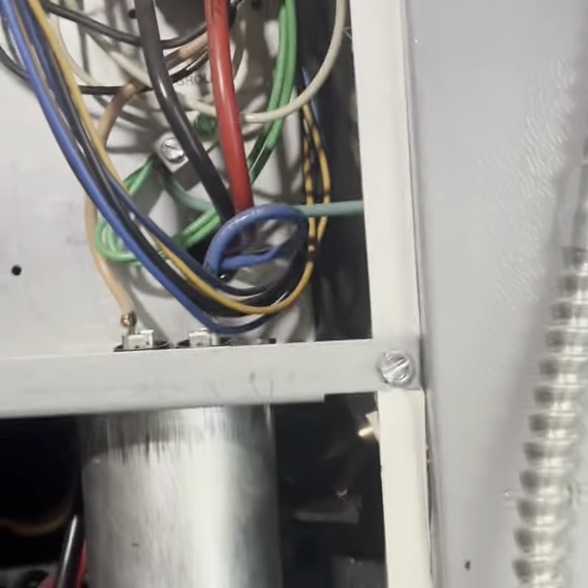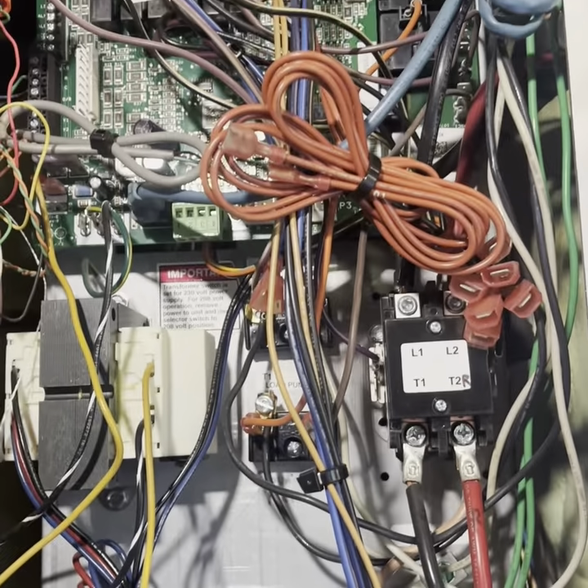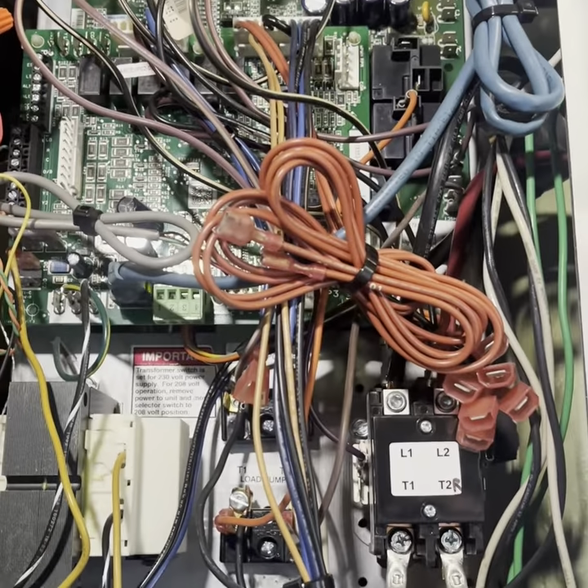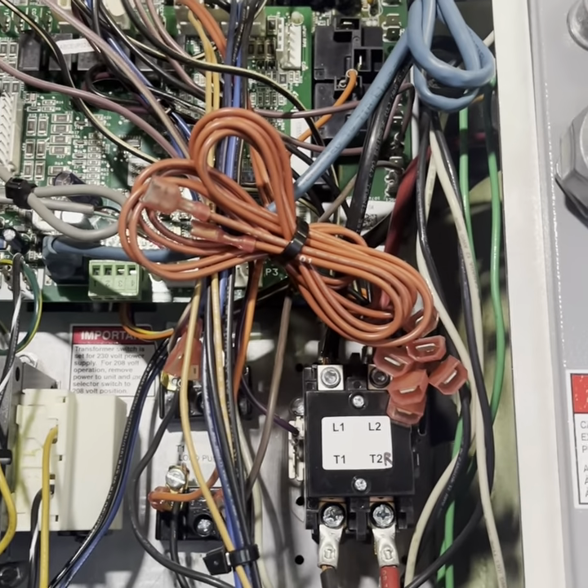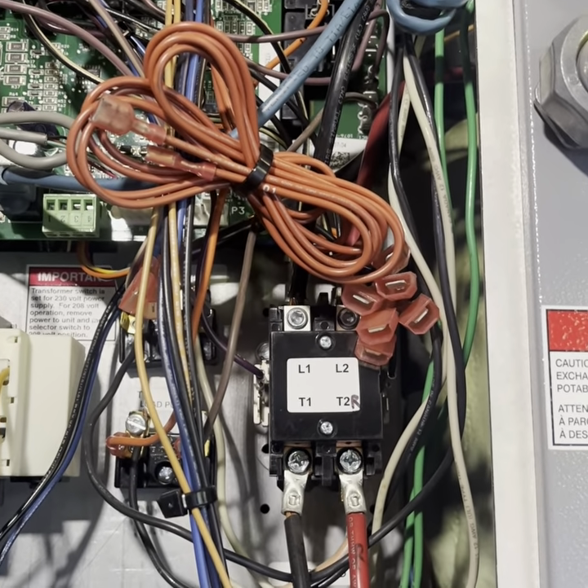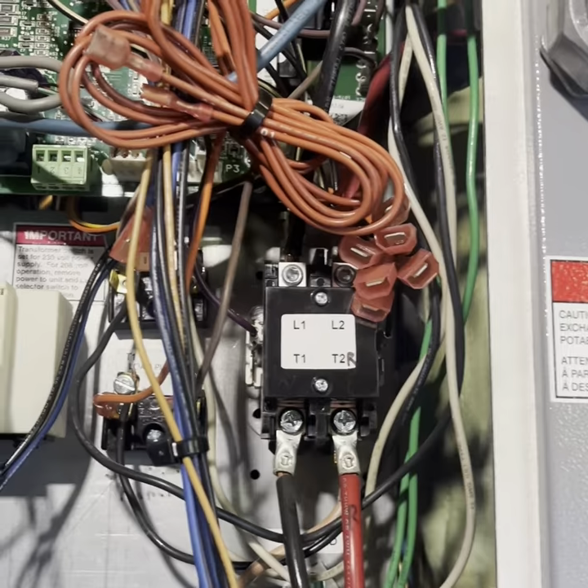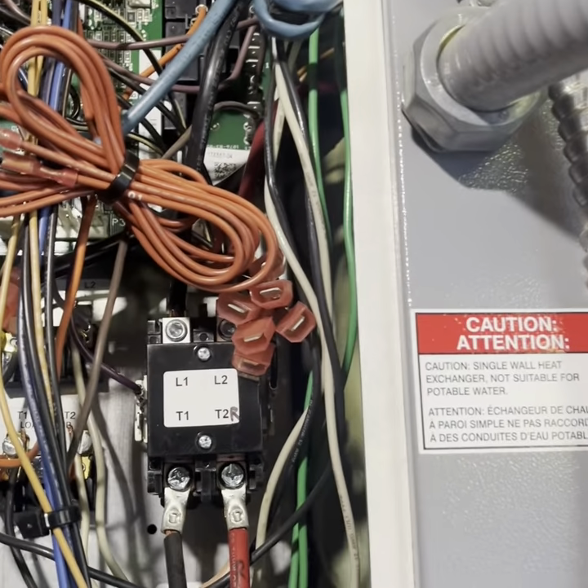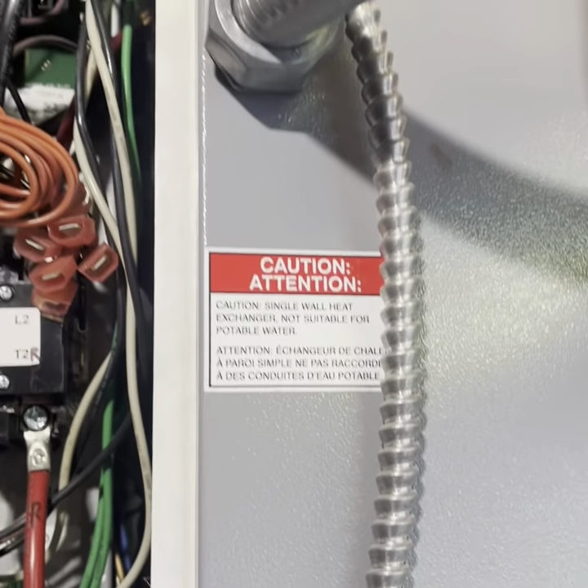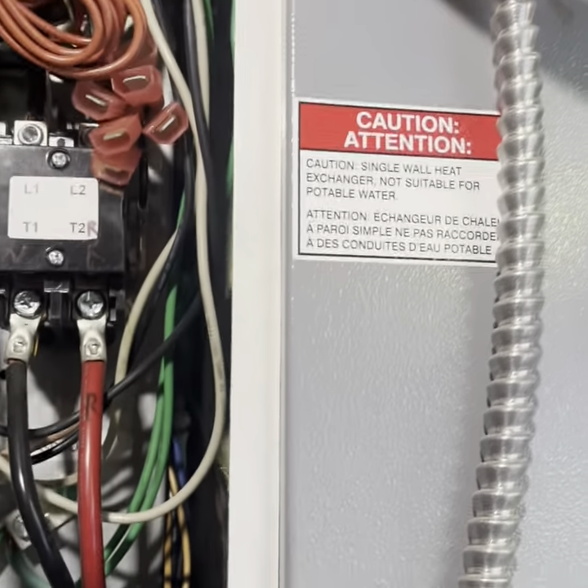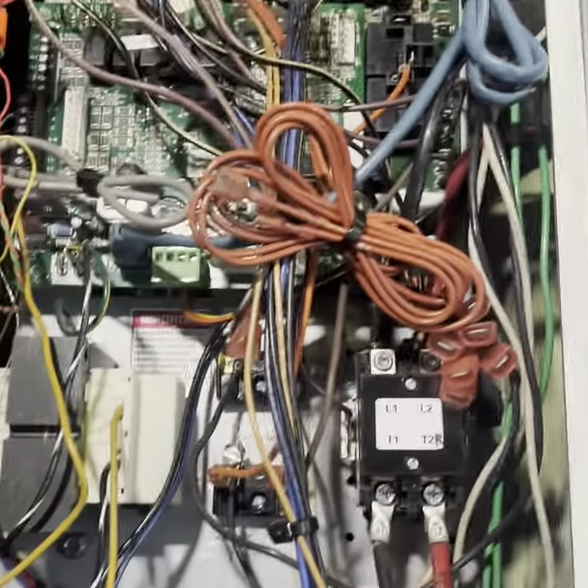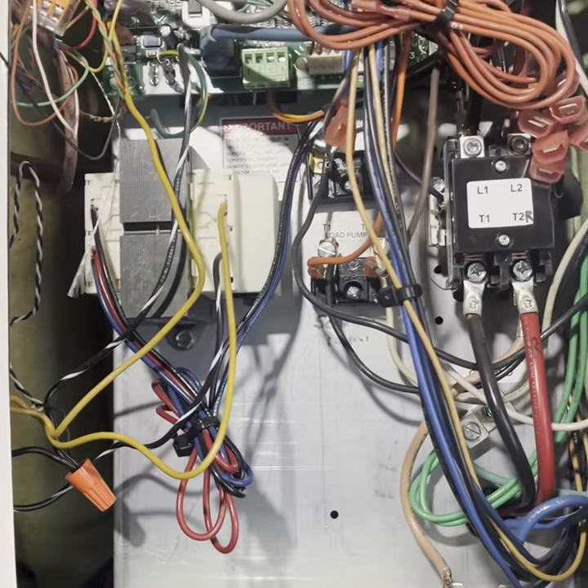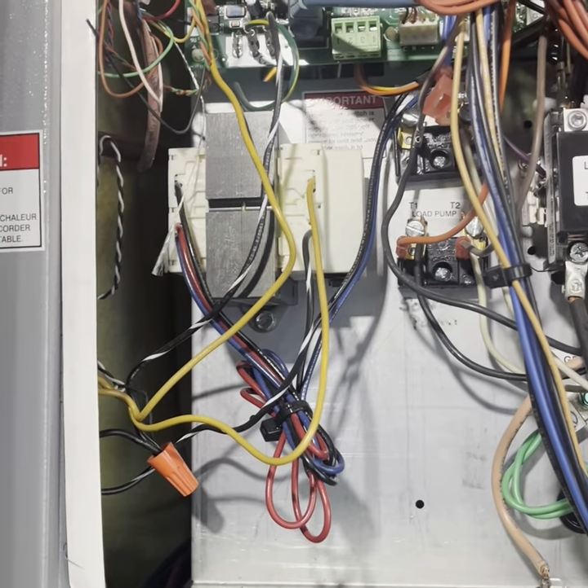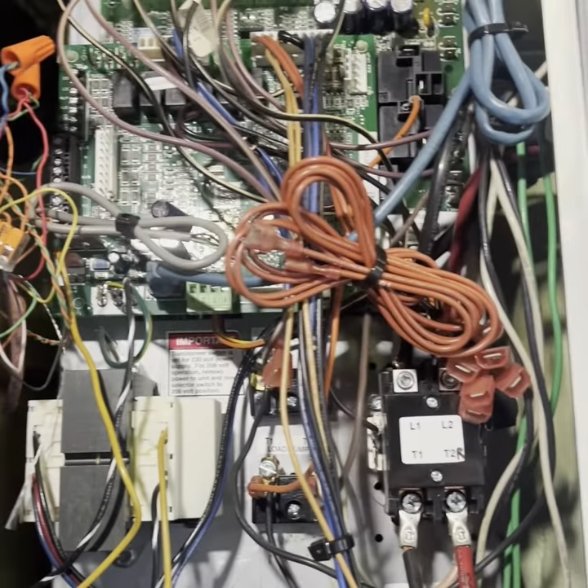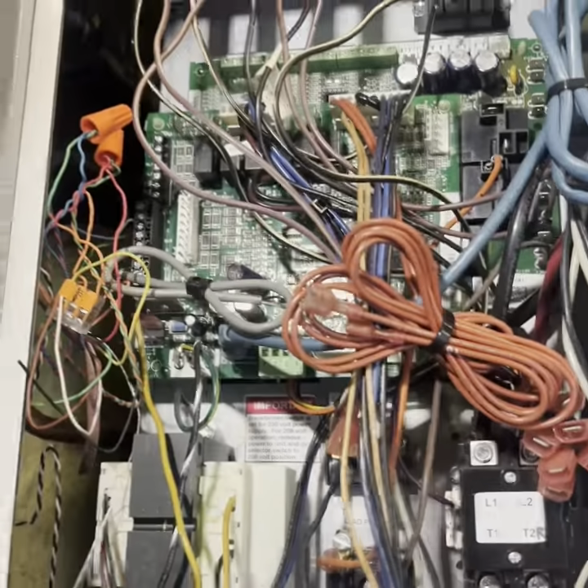We basically redid everything that was installed by a pool company. They undersized the pipes, undersized the heat exchanger. None of the controls were set up right. There was no thermostat even controlling it, it was just running 24/7 without demand. We've gotten all of those problems rectified except the last issue, which is all the pumps run 24/7.